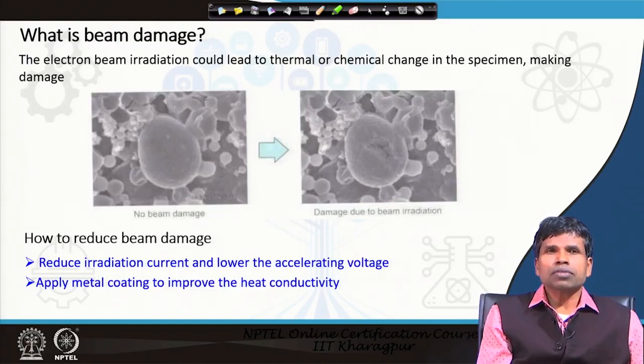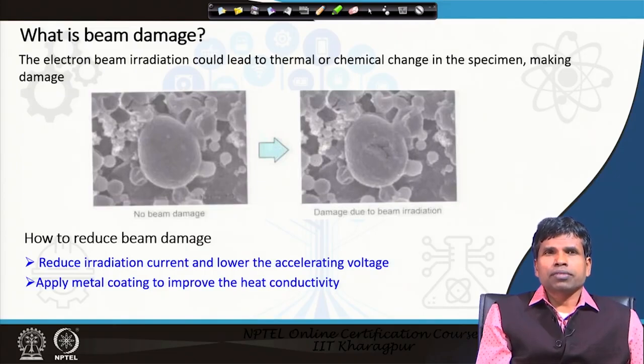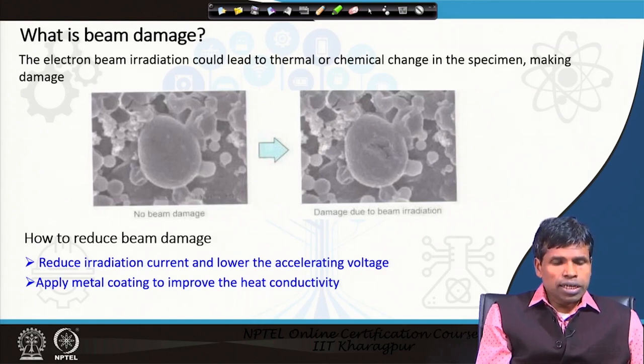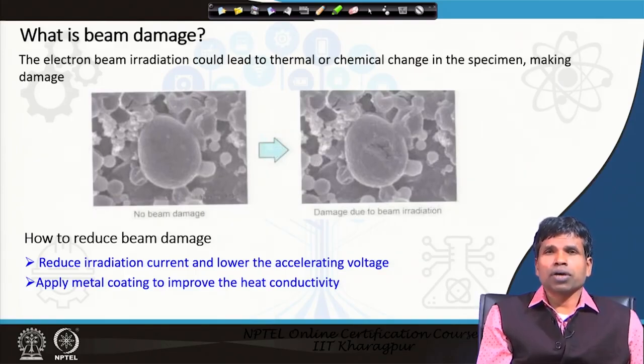Polymer and biological samples are most commonly examined with acceleration voltages in the range of 1 to 3 kilovolts. On the other hand, oxide and metal-type samples can be done at more than 5 kilovolts. Another way to reduce beam damage is to apply a metal coating to improve heat conductivity — a thicker metal coating will also help protect biological or polymeric samples from damage to a large extent.